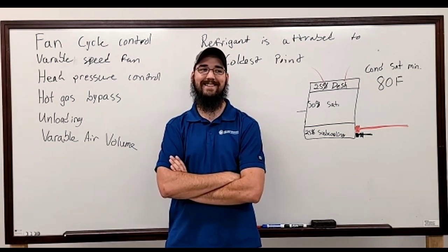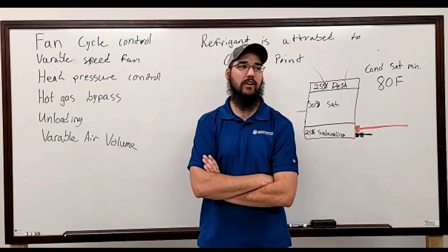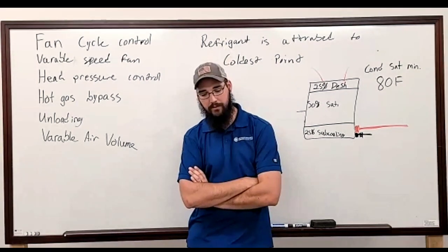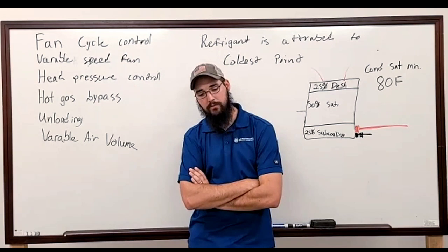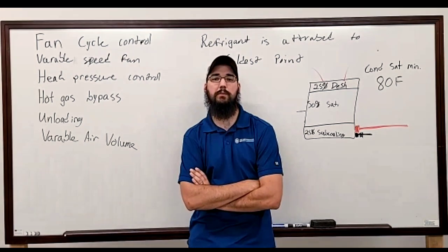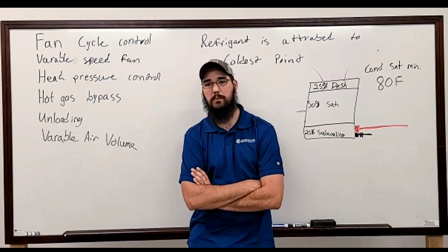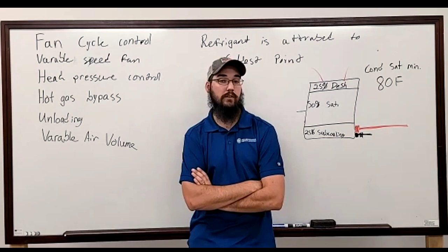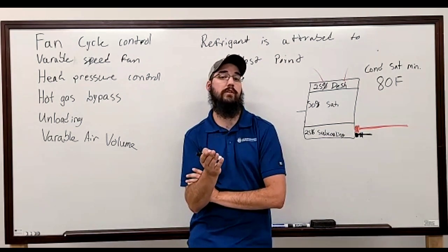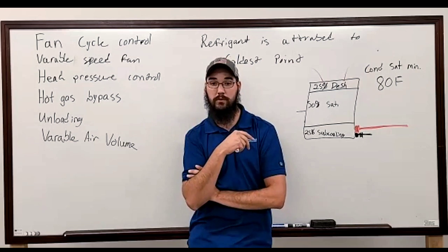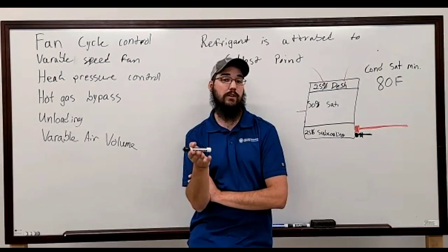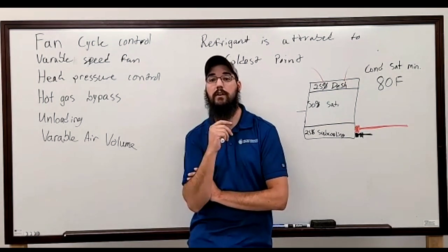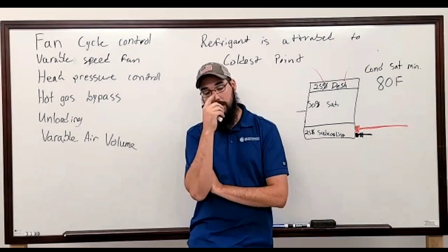Well, they're related. So the question for everybody online is about the compressors themselves being variable speed, whether they'll be VFD or inverter driven. And even taking it further, them being more than 60 hertz motors, 200 hertz motors, right? Actually, it's not uncommon at all, given that a lot of the VRV systems will run significantly higher hertz than that.